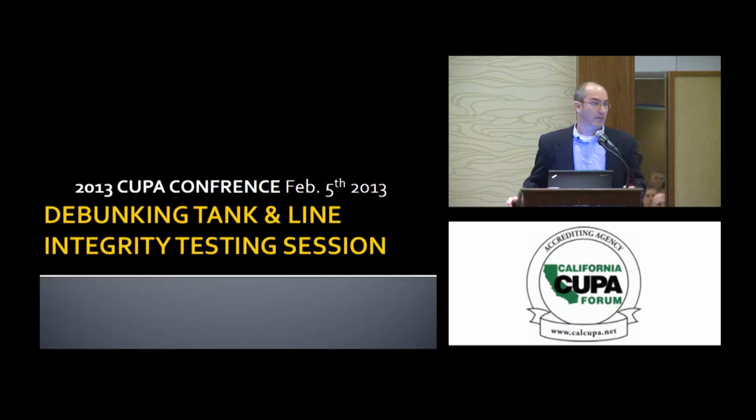The non-volumetric was a different category, which said, hey, there are other technologies that exist that may not quantify a leak rate, but they can give a yes-no answer to determine if a tank is leaking. Those use technologies like acoustic or possibly ultrasonic listening. It could be a vacuum or a pressure decay test or a tracer gas technology. And there are many examples of those types of tests as well.